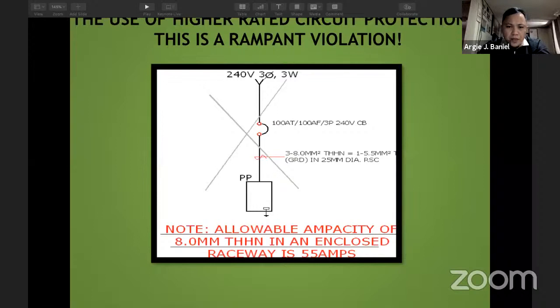This single line diagram indicates the breaker used is a 100 ampere trip breaker, while the wire used is 8.0 square millimeter THHN. The ampacity of this 8.0 THHN wire is only about 50 amperes trip; if it were THW or TW, it would only be 40. So it will overload when used, but the breaker won't trip because its rating is higher than the load and the wiring system.